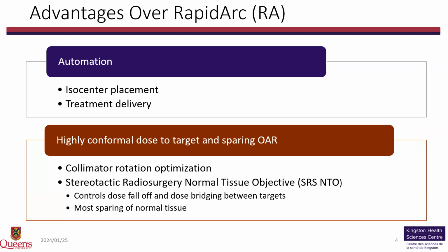So for planning of the HyperArc treatment, it uses a specific normal tissue objective, which is called the stereotactic radiosurgery NTO, or in short, SRS NTO. So this SRS NTO controls the dose fall off and the dose bridging between the nearby targets, which in turn will produce a plan that will generate a highly conformal dose to target while sparing normal tissues and the important OARs.